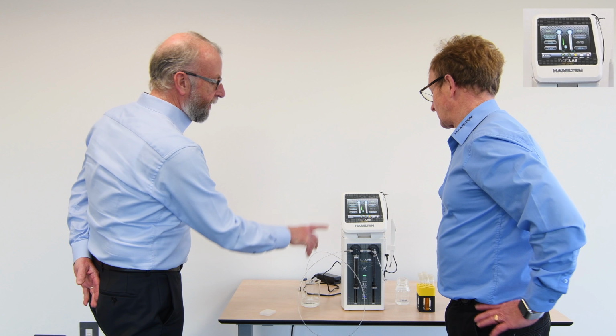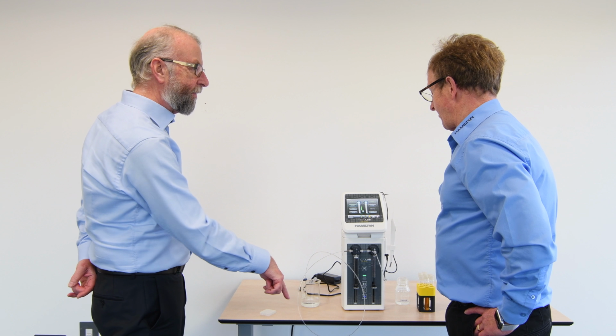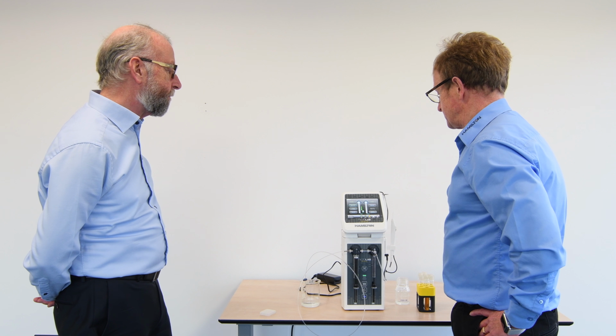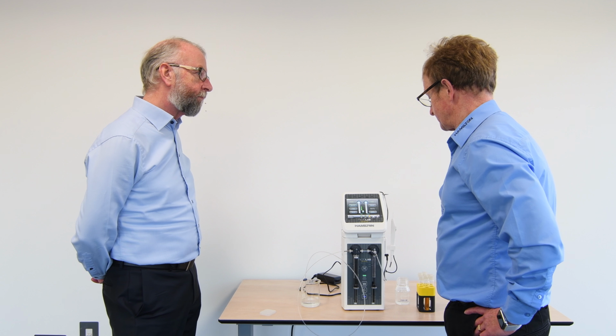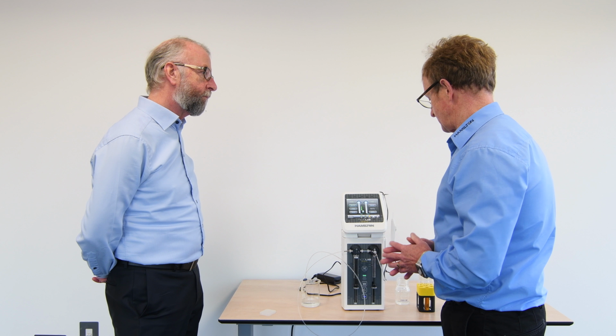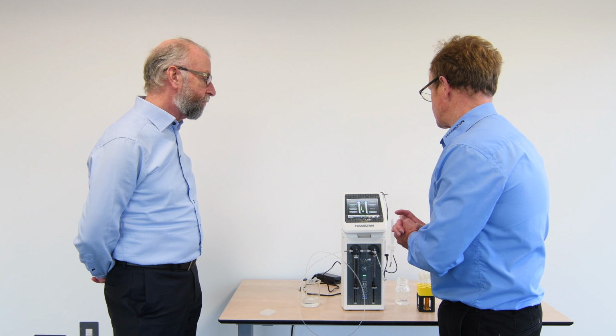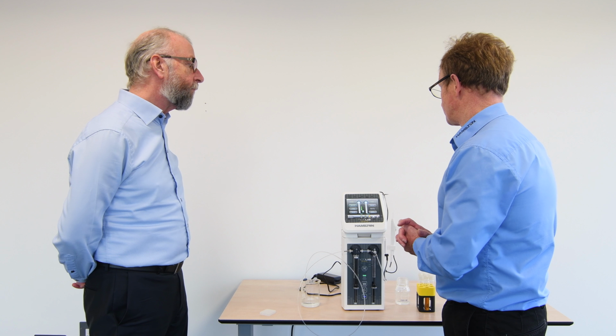So the wash volume, the syringe driver will determine the number of strokes of the syringe. Is it limited by the maximum volume of the syringe? No, it will actually select a volume which is appropriate. So if I want to do a really high dilution volume afterwards, then I can select larger than the syringe size. But let's, for example, say you asked about your sample, which was 500 microlitres.